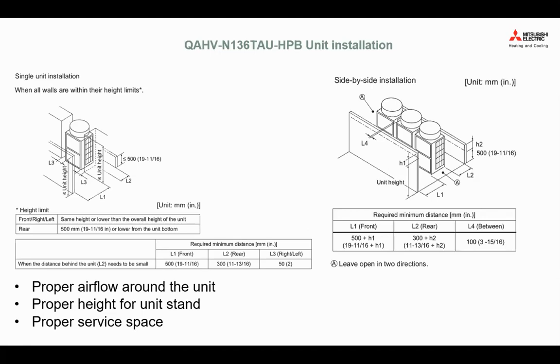And again, the next thing is proper height for the unit stand. The unit should be placed on a stand, because in wintertime there may be ice or snow accumulation, especially if you install it outdoors, and we want to avoid that. So you really have to specify a proper height for the unit to be placed above the local snow line.